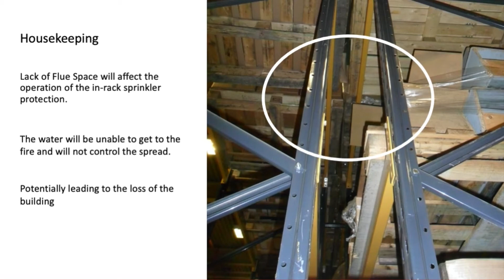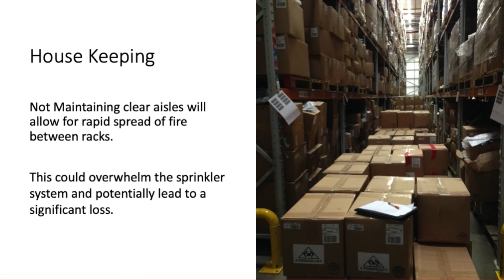Another thing, when we talked about the aisles, the main reason for having the aisles is so that forklifts can get down there, but if it's over 2.4 metres wide, we need that 2.4 so the fire doesn't spread from one rack to another. So when you get a situation like this where we're just storing stuff down the middle of the aisles, if we're only calculating it on one rack in operation, that fire is going to quickly spread from one rack to the other through the goods stored between them. So that's going to overwhelm your sprinkler system again. So again, it's all about housekeeping. So once the system's installed, we need to make sure that the housekeeping's kept up to date, etc., etc.